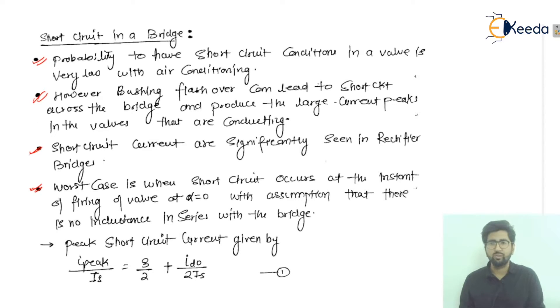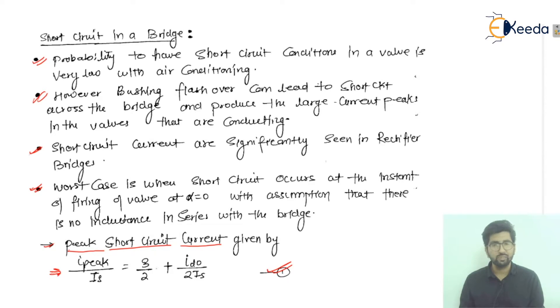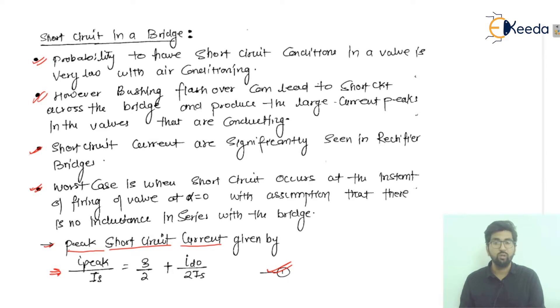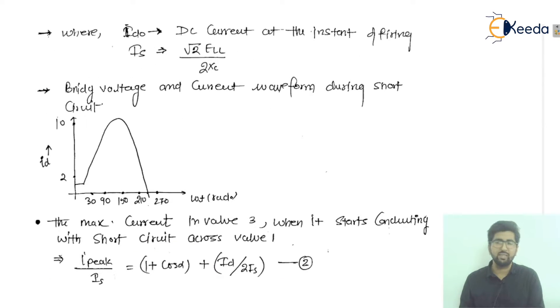The peak short circuit current formula is: i_peak / is = 3/2 + id₀ / (2·is). This relation is found from derivation — we are not going through the derivation, just concentrating on the important points. So: i_peak / is = 3/2 + id₀ / (2·is).